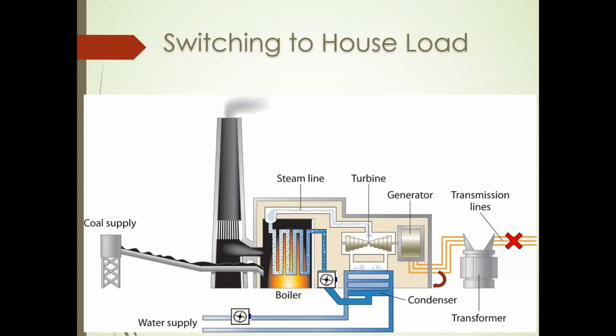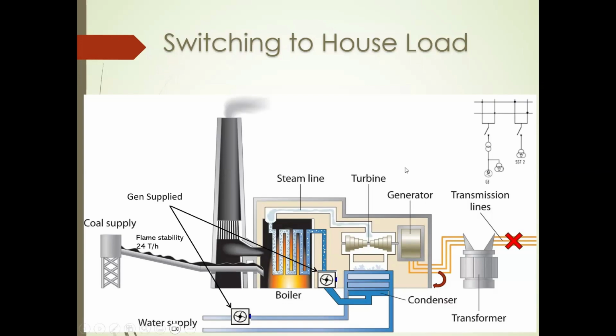Now here, what happens is that the generator can provide power to these two pumps. Actually, the system will not notice any disruption to the station 6 kV auxiliary supply, so all the auxiliary equipment, the cooling water pumps, lubrication oil pumps, will work and will never notice a power disruption. So the unit will continue running with its own auxiliaries and can be synchronized back to the grid.